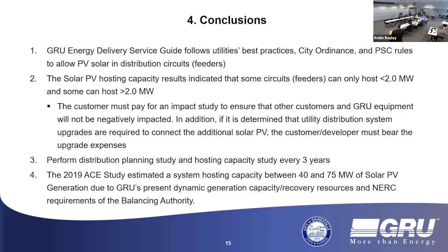You might think that if we average, say, 2 megawatts per circuit and have roughly 70 distribution circuits, we should be able to host 140 megawatts of solar PV total without issues. But we have another limiting factor based on our present generation portfolio. The 2019 area control error study estimated that GRU is limited to hosting between 40 and 75 megawatts of solar PV, due to GRU's present dynamic generation capacity and recovery resources, and NERC requirements of the balancing authority.